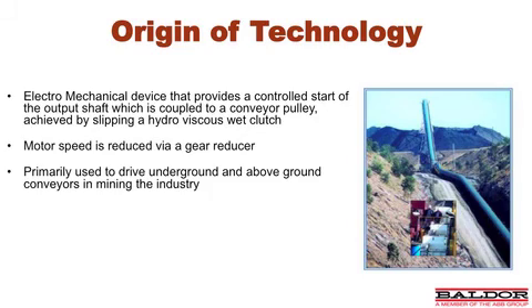This technology was originated years ago within our company for conveyor applications, where these are very long conveyors, primarily in the mining industry. It's an electromechanical device that provides a controlled start of the output shaft, which is coupled to a conveyor pulley, achieved by slipping a hydroviscous wet clutch. The motor speed is reduced via a gear reducer, primarily used to drive underground and above-ground conveyors over miles of distance, and again, as I said, typically in the mining industry.